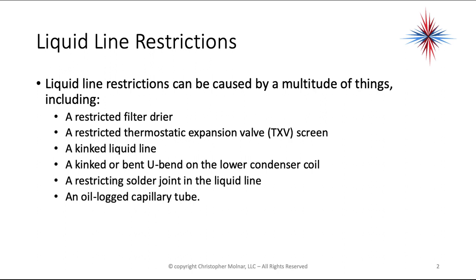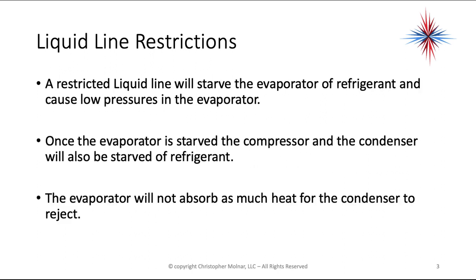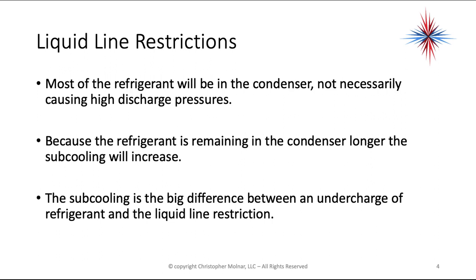An oil-logged capillary tube is one you'll have to look for after ruling everything else out. A restricted liquid line will starve the evaporator of refrigerant, causing low pressures in the evaporator. Once the evaporator is starved, the compressor and condenser will also be starved. Most of the refrigerant will be in the condenser — not necessarily causing high discharge pressures though, because most condensers are sized to hold 100% of the system charge. Because the refrigerant stays in the condenser longer, sub-cooling will increase.